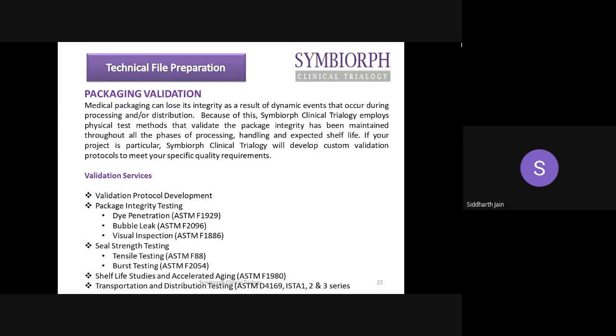All these requirements and stability studies are performed, and we have to submit them to determine the shelf life of your product. If your product has a shelf life of 5 years, you also have to perform accelerated aging studies and real-time stability studies. Being a startup company, you cannot submit all 5 years of data of the real-time stability studies. For that reason you have to submit the accelerated aging studies as per the requirement of ASTM F1980. If you read the standard very carefully, it talks about the Arrhenius equation. So if the shelf life of your product is 5 years, depending upon the Arrhenius equation, you have to calculate the accelerated aging study timeline. Typically it will vary from 2 months to 6 months. Depending upon that, you have to keep the samples for stability testing under the accelerated aging studies.